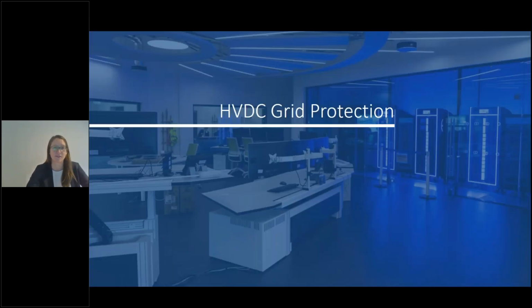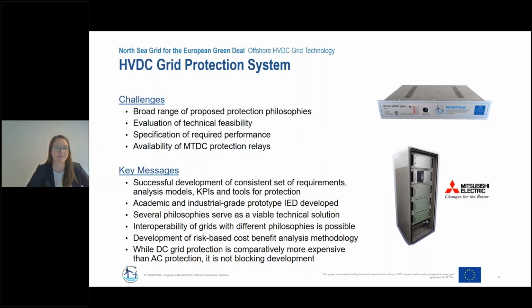With the DC circuit breaker being one element of HVDC grid protection, let's look at the work done on HVDC protection. Again, there's not one standardized DC fault clearing strategy, but a broad range of protection philosophies, and evaluating technical feasibility was not possible in the beginning. There was no set of required performance or key performance indicators to compare the different proposed strategies and their implementation in different grid structures.